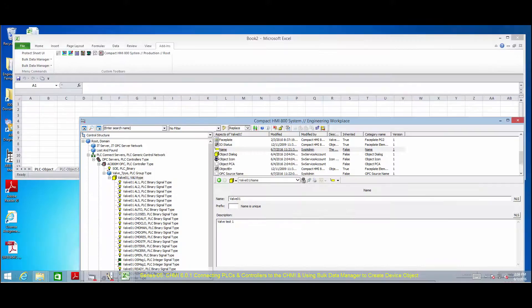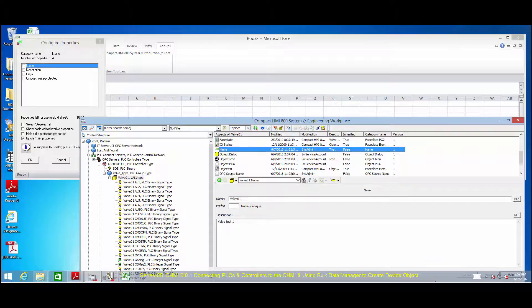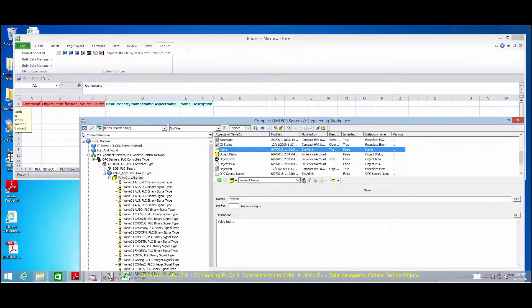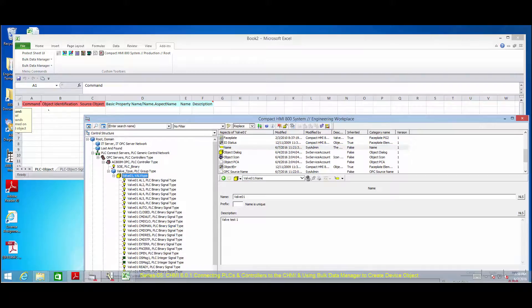This scenario shows you how to add a second Valve object on the control structure using BDM. Click the device object Valve 01 and select the name aspect. Drag and drop the name aspect to Microsoft Excel and configure the desired properties using the configure properties window as shown. The next step is to drag and drop the Valve 01 device object from the control structure to Microsoft Excel.